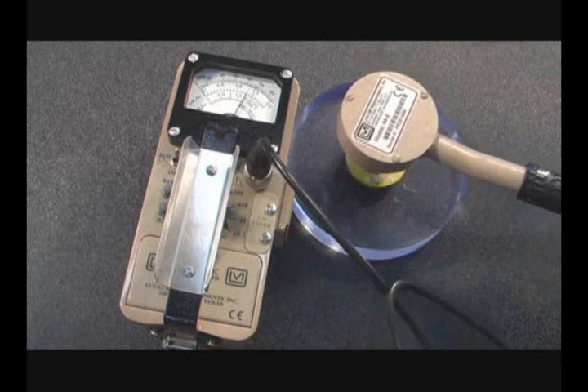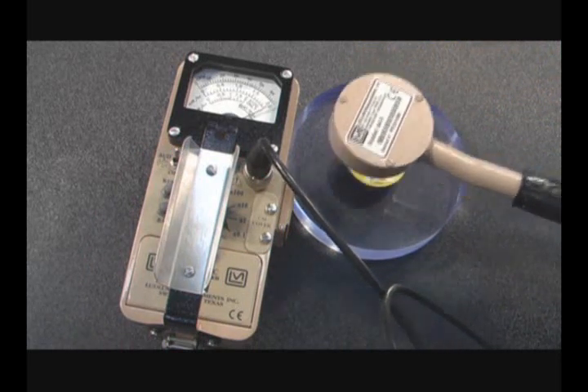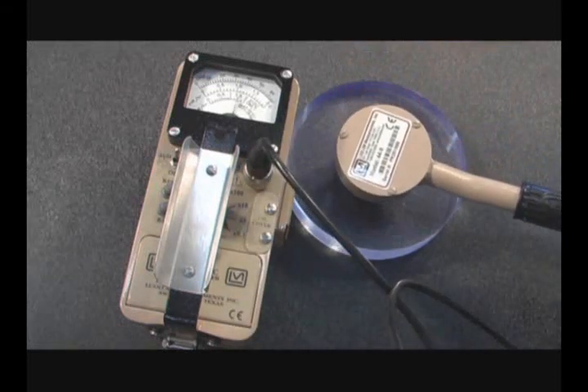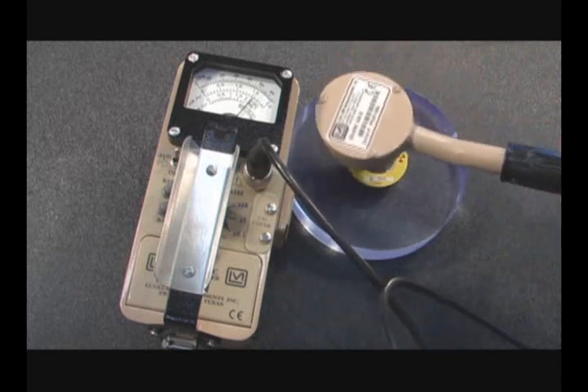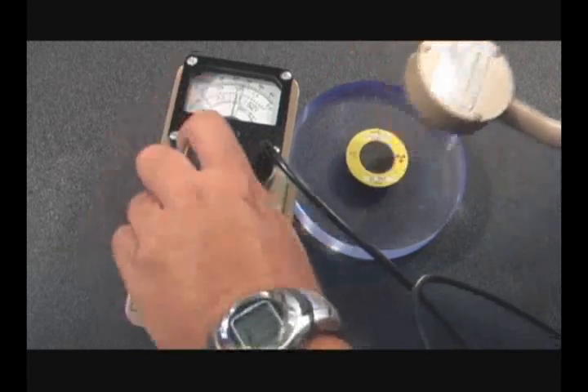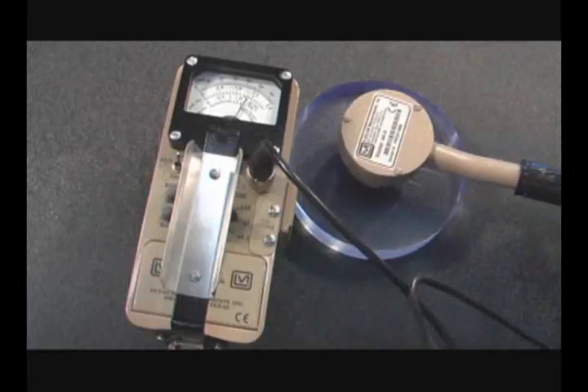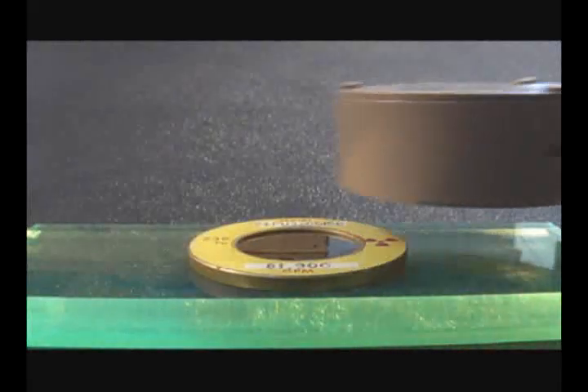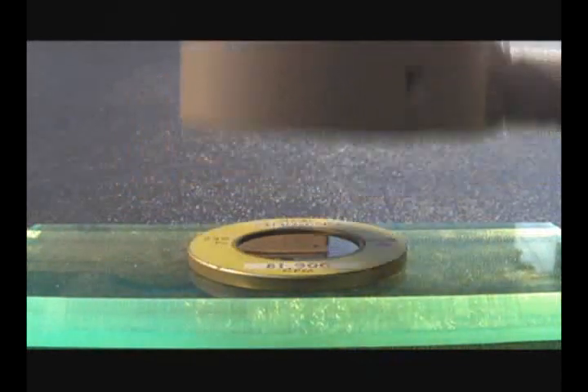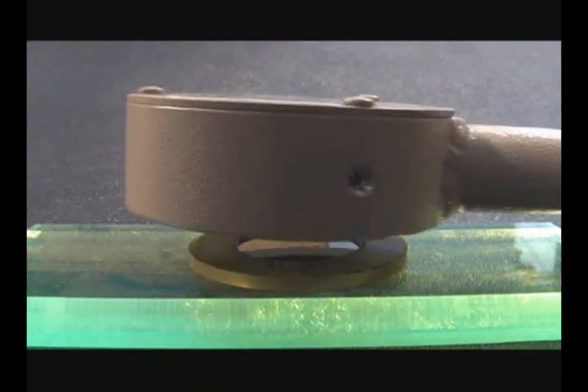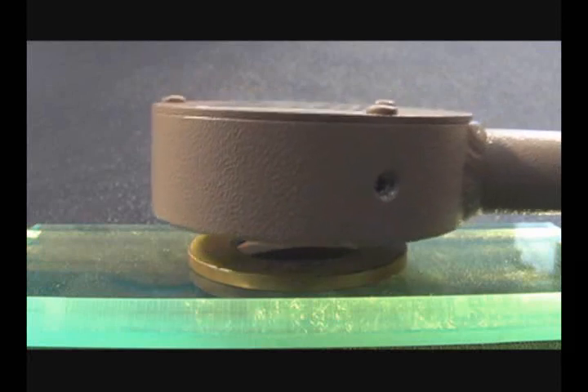The CPM scale is always used for measuring alpha radiation. When the detector approaches the alpha source, the audio count rate in audio clicks will increase. Every time the needle is driven to full scale, switch to the next higher range multiplier position. Notice that the alpha particles are only detected when the Model 44-9 is moved very close to the source. Alpha particles only travel about 1/2 inch through air.